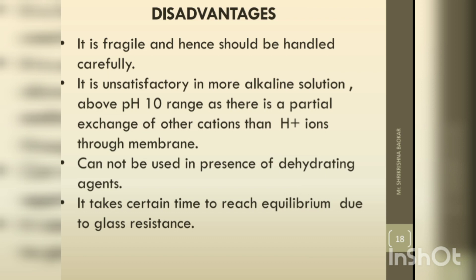Disadvantages: It is fragile and can easily be damaged, so it should be handled carefully. It is unsatisfactory in more alkaline solutions above pH 10, as there is a partial exchange of cations other than H+ ions through the membrane. It cannot be used in the presence of dehydrating agents such as concentrated H2SO4. It takes certain time to reach equilibrium due to glass resistance.